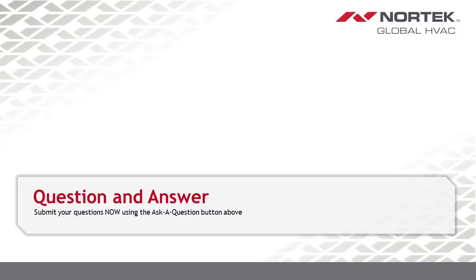Okay, we have another question coming in about what CFM per ton is targeted for all the cooling applications on these furnaces. Yeah, we're looking to target around 400 CFM per ton with each cooling tap to match the applicable tonnage. For instance, one furnace could cover 2 through 4 tons of cooling, so one tap would cover 2 tons times 400 CFM. That tap would target 800 CFM for the cooling application.